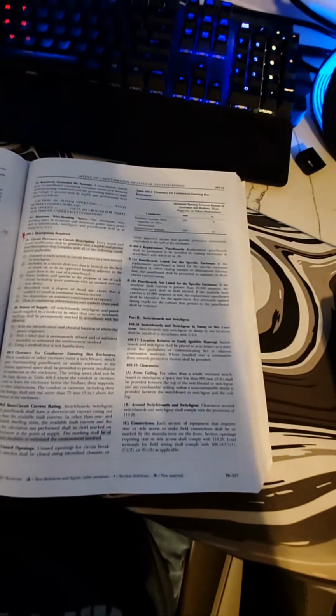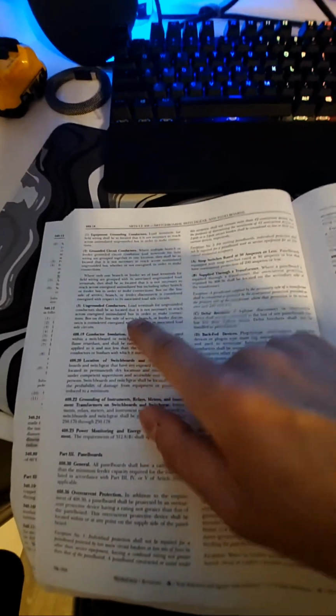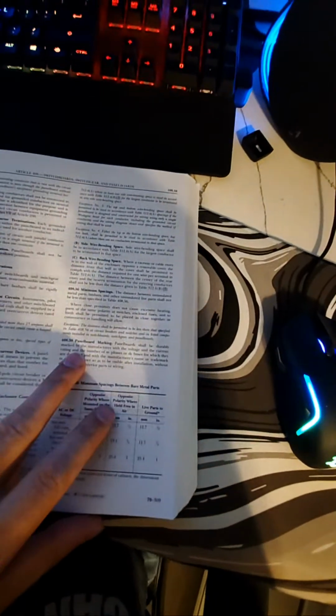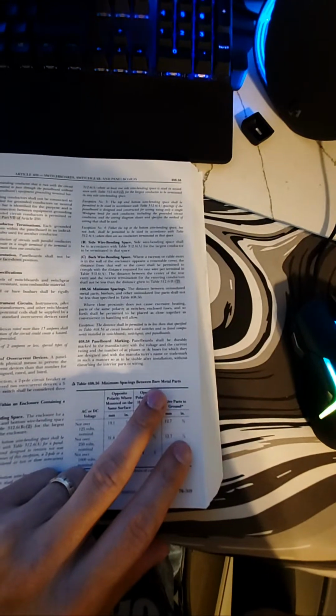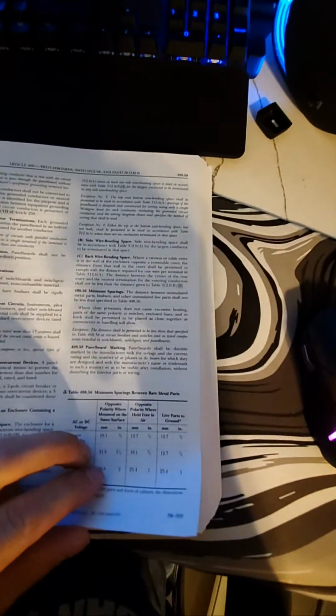I'm going to kind of skim through here too, just to see if I can find it. Here's a directory, so this would be marked. Here's a clearance. I'm not seeing marking specifically yet. That's the grounding, location. Still don't see it here. Panel board marking. 408.4b, you think so? We'll go back and look at it. Here's industrial control panels. This said industrial occupancies too. Location, rating, phase arrangement, marking. Industrial control panel shall have permanent markings that are visible after installation.